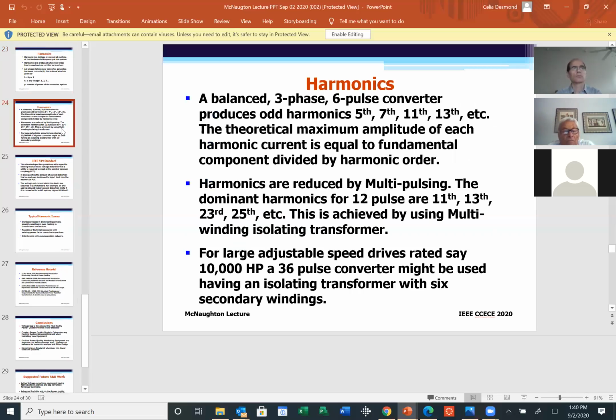Next slide, please. These are typical harmonics that are produced by a balanced three-phase, six-pulse converter, which are the 5th, 7th, 11th, 13th, and so on. The problem with harmonics is that they cause several issues, just like the voltage sag, but this is different.